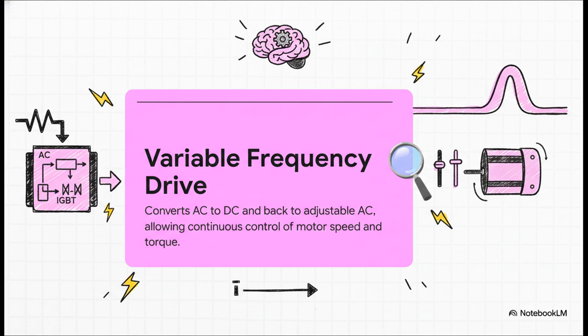It takes the regular AC power coming in from the wall, converts it into DC power, and then from that DC, it builds a brand new, perfectly sculpted AC signal from scratch, and that lets it adjust both the voltage and the frequency on the fly, giving it total command over the motor's speed at any moment.